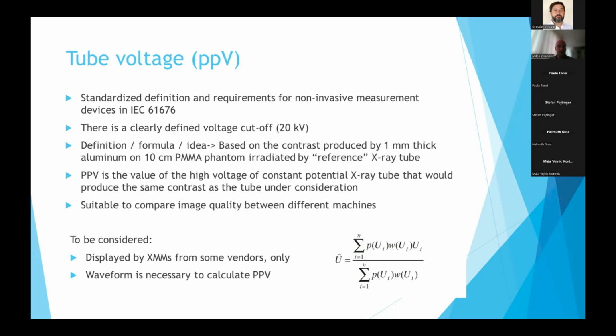So another advantage is that there is a very clear definition in the standard. There is also a clearly defined voltage cutoff, because you can see the formula here for calculation of practical peak voltage. So there are weighting factors that are used, and below 20 kilovolts, these weighting factors are 0. So you know when you should start the measurement, when you should stop the measurement. It is all clear. And the disadvantage is that only a few XMMs can show you this quantity. So even if you want to measure it, it is highly likely that your XMM cannot actually measure it, that it doesn't provide you the value for this quantity.